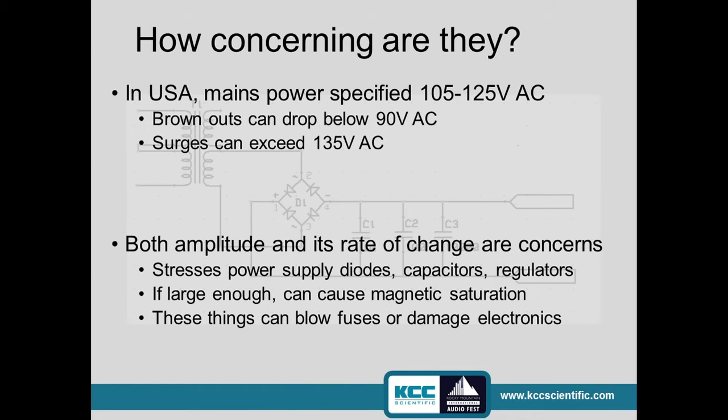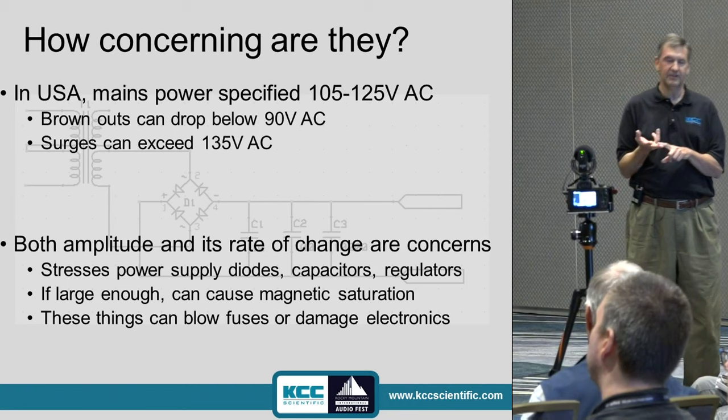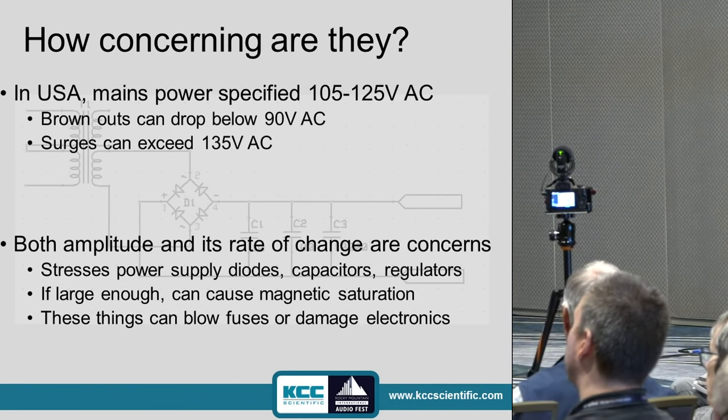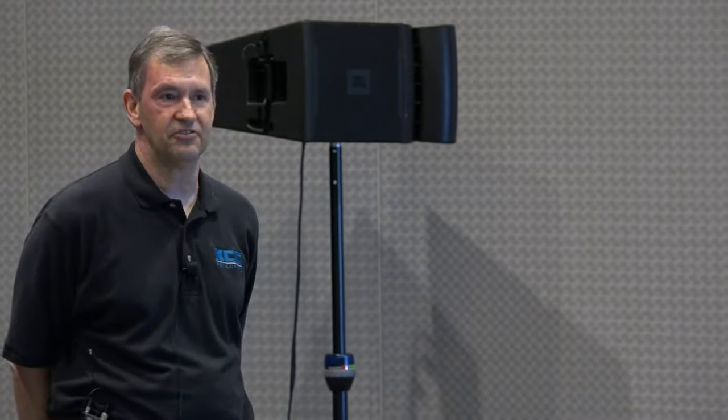In the US, the power supply is specified between 105 and 125 volts AC — that's a pretty wide range. I've observed brownouts in various locations that have dropped well below 90 volts, and surges that have exceeded 135 volts for reasonable periods of time. It's not just the amplitude itself but also the rate of change. Things that happen more rapidly than the electronics is designed to tolerate really get you. If you get the voltage big enough, it can saturate the magnetics in your power transformers and audio equipment — blown fuses, damaged circuits, even exploding capacitors.